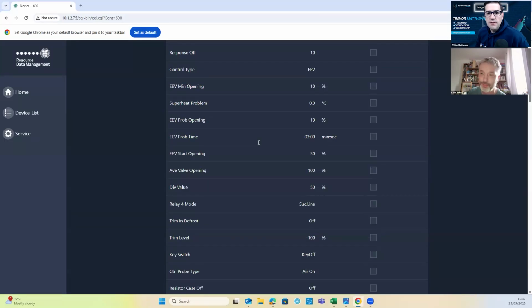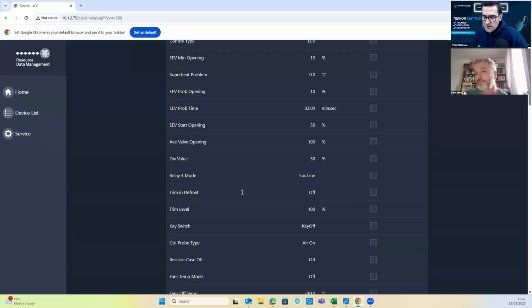But a classic example of evolving parameters, I plugged this controller in earlier to set it up, and I couldn't change parameters on it. The reason being, if I'd read the manual, RDM have changed the security structure now, so you have to change a setting to let the data manager alter settings for you. And if I'd actually read the manual before I plugged it in, I would have known they'd done that. So, read the manual.